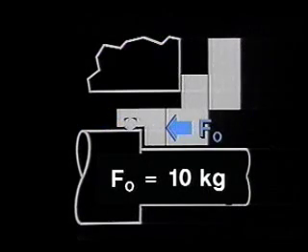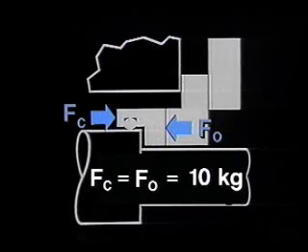The opening force is the same as calculated in the previous example as both the pressure and area remain unchanged. Now we have 10 kilograms of closing force and 10 kilograms of opening force. The opening and closing forces have been completely balanced.